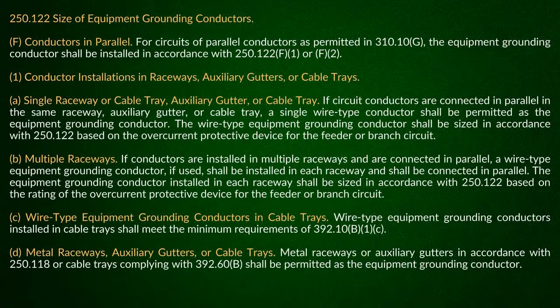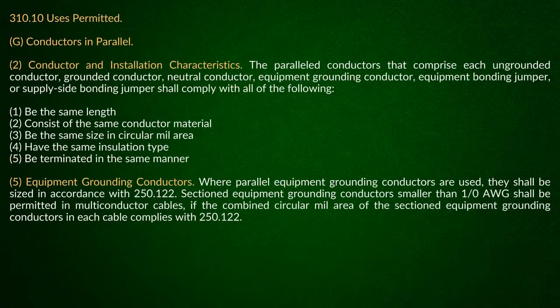Table 250.122. Now, I'm going to prove that point right here, because when I go over and look at 310.10(G), and (G)(2) talks about the conductor and installation characteristics all being the same length, consisting of the same material, the circular mil. Here's a spot where it talks about them all being in the same circular mil area. Then you come down and pick up number 5, and what does it say?